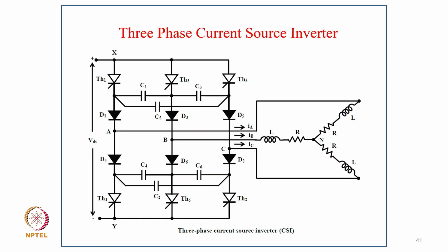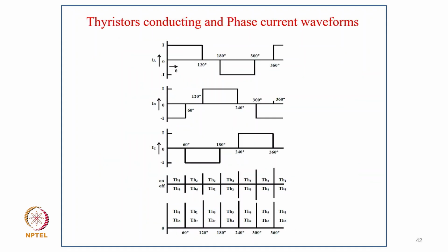And these are three-phase current source inverters, which were used extensively earlier for induction motor drives, and the capacitors and diodes are only required for commutation of the thyristor. And so this commutation circuit was cheaper, so it has become quite popular as well as reliable. But of course, the limitation is that you cannot increase the switching frequency beyond a certain limit because of this additional commutation circuit.